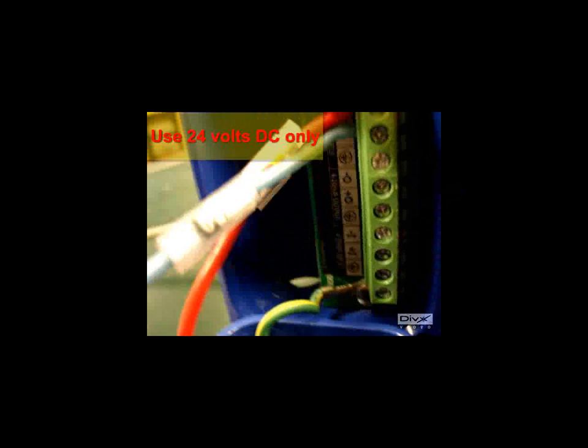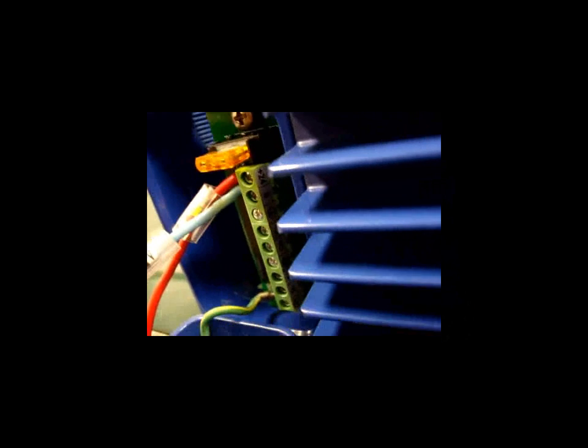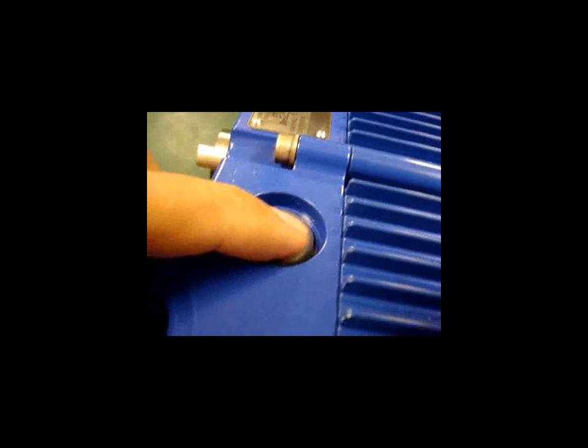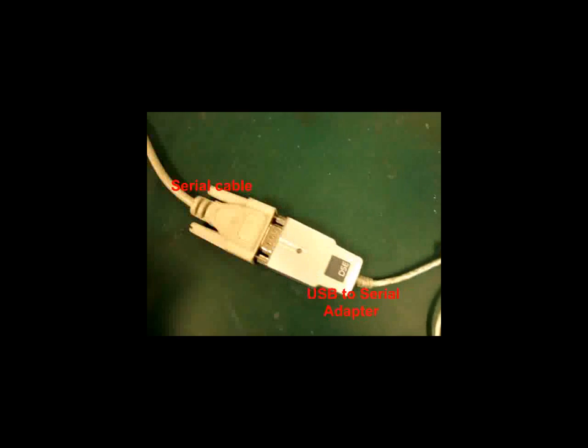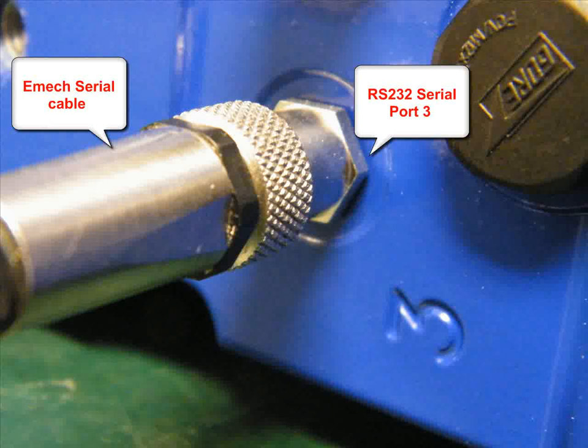First step is to connect the power supply terminals of the actuator to a 24 volt DC power supply. Then you turn on the actuator by pushing the green button and holding it for about 2 seconds. Connect one side of the USB to serial adapter cable to your PC or laptop's USB port. Then connect the other side of the cable to the supplied serial cable. Then you screw the serial cable onto the port labeled 3 on the underside of the actuator.